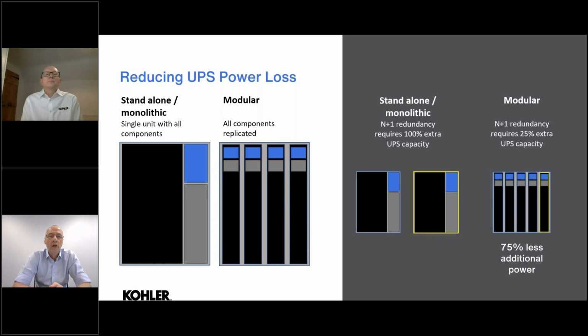Now, what this means is when we're looking at a data center, we're always going to want redundancy, and typically N+1 redundancy. Now, if we were having the monolithic standalone systems, we would just add another unit on, potentially having an extra 100% extra UPS capacity. So instead of that, if you were doing it with the modular systems, the example shown, we would just add an extra module and just an extra 25% capacity, 75% less additional power infrastructure UPS than would have been done with the standalone monolithic type units.